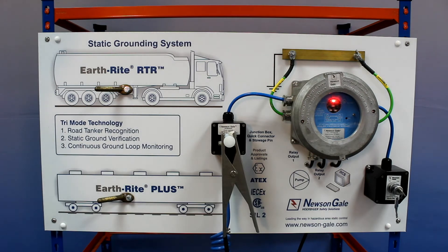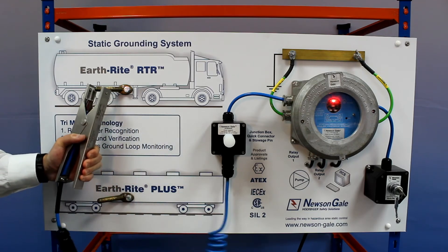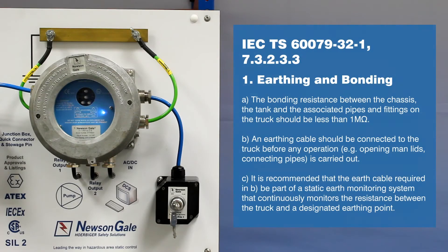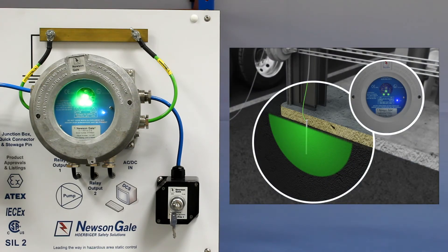Only once these outputs are met will the system show a permissive state, indicated by three pulsing attention-grabbing green LEDs, and energise whatever equipment such as a pump to control the flow of product to or from the road tanker. Interlocking with the transfer process means product flow can be halted should the connection exceed 10 ohms. Any static generated by the loading operation is transferred from the road tanker via the Earth-Rite RTR to ground, mitigating static electricity as a potential source of ignition.